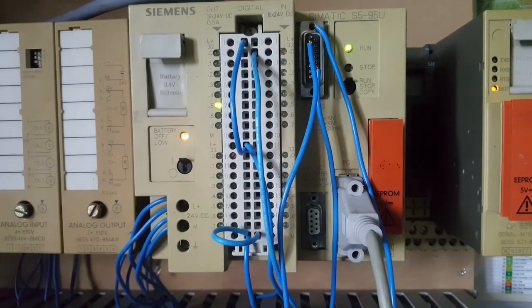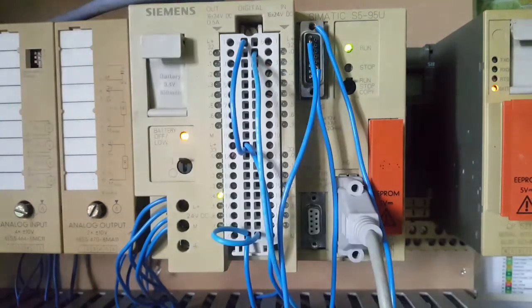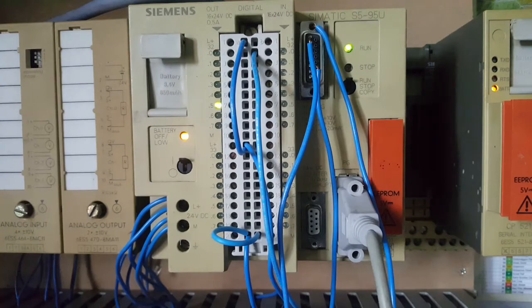So as can be seen here, I am using an S5 95U brick type PLC. These PLCs have 16 digital inputs here and 16 digital outputs here on board, as well as 8 analog inputs and 1 analog output, which can be accessed via this 15-pin connector here, not to be mistaken for the 15-pin programming port here.